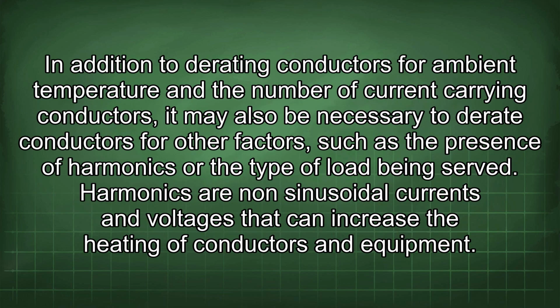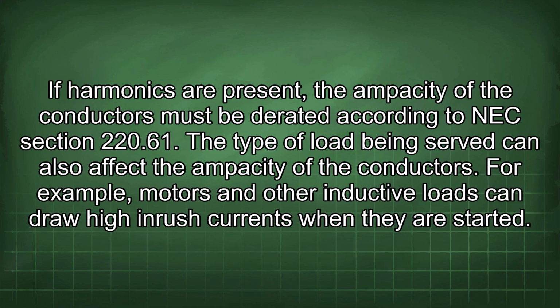In addition to derating conductors for ambient temperature and the number of current-carrying conductors, it may also be necessary to derate conductors for other factors, such as the presence of harmonics or the type of load being served. Harmonics are non-sinusoidal currents and voltages that can increase the heating of conductors and equipment. If harmonics are present, the ampacity of the conductors must be derated according to NEC section 220.61. The type of load being served can also affect the ampacity of the conductors. For example, motors and other inductive loads can draw high inrush currents when they are started.